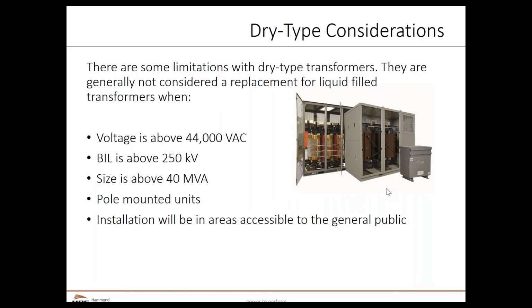And if there are areas that are accessible to the general public, liquid-filled transformers often have some advantages. As an example, behind our house in our subdivision here, we have a little green transformer case. It's liquid-filled. It's about the size of half of an oven. It's only about 2.5 feet tall. Kids go climbing on it. That is a hermetically sealed unit. And I don't like the kids climbing on it. In fact, I take them off. They shouldn't be. But a completely ventilated unit probably is not a good idea to install in an application like that, again, because it has a lot of accessibility to the general public.